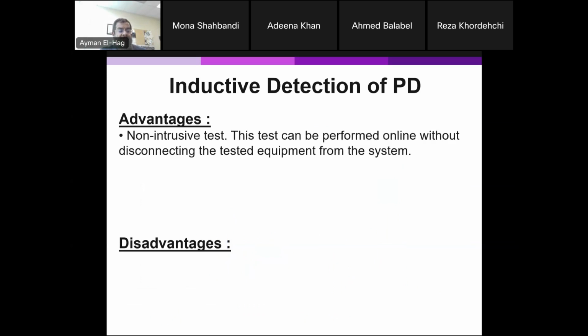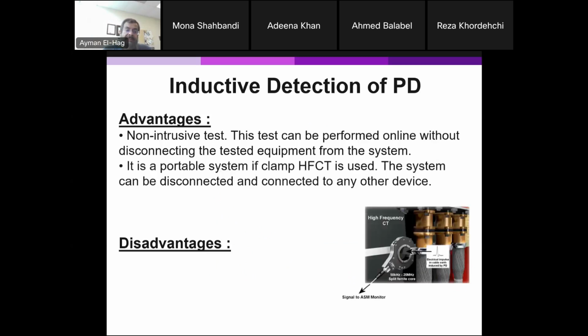Now, what are the advantages? It's non-intrusive. Non-intrusive meaning that you don't need to interrupt the power. You just need access to the ground. Okay, so that is something very important, especially in the field. In the field, if you want to measure the partial discharge, the technique has to be non-intrusive. Because if it is intrusive, then you have to take the unit out of service, power interruption. This is a lot of problems, and that's not easy to be coordinated.